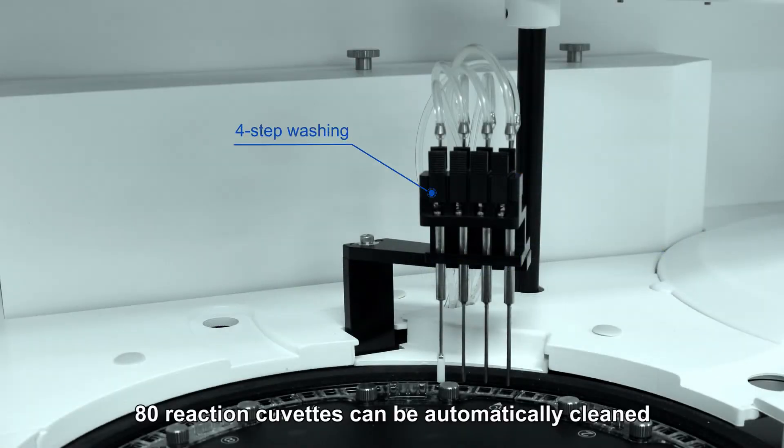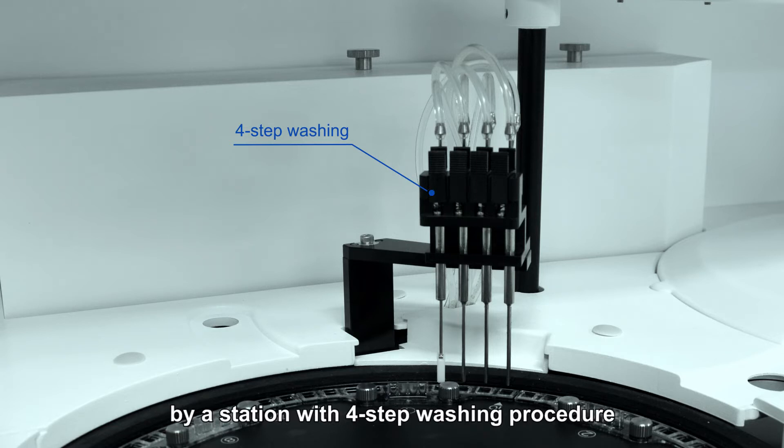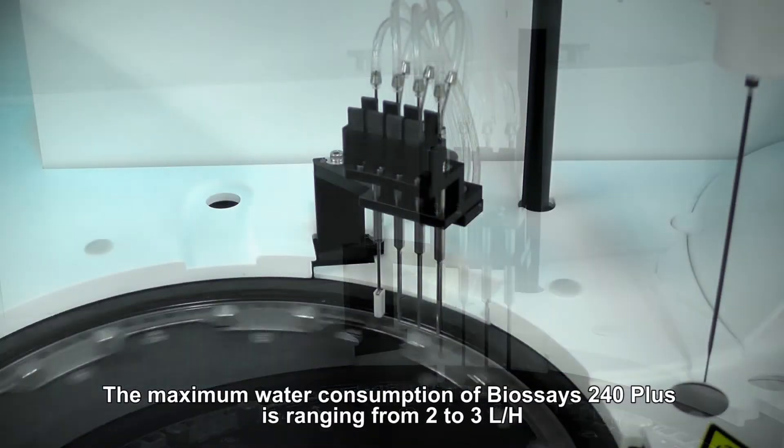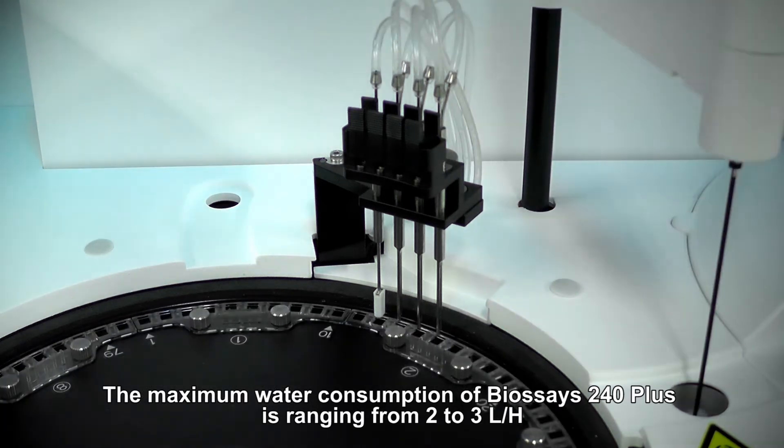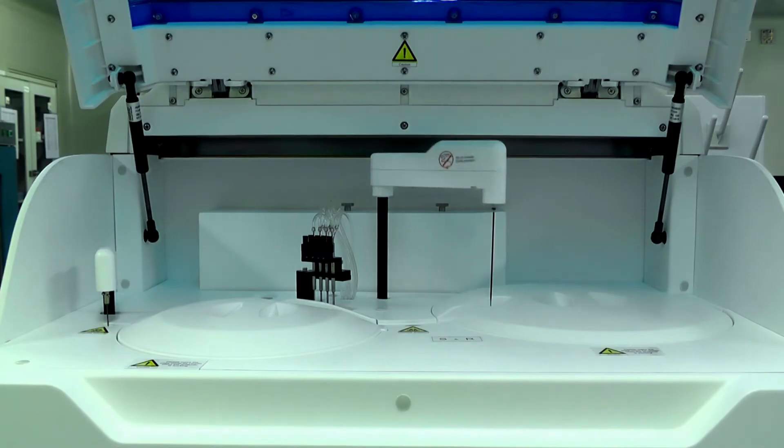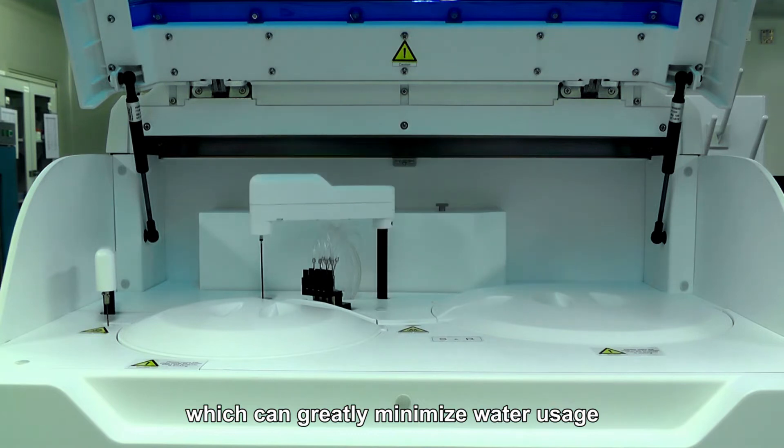80 reaction cuvettes can be automatically cleaned by a station with 4-step washing procedure. The maximum water consumption of Biossays 240 Plus ranges from 2 to 3 liters per hour, which greatly minimizes water usage.